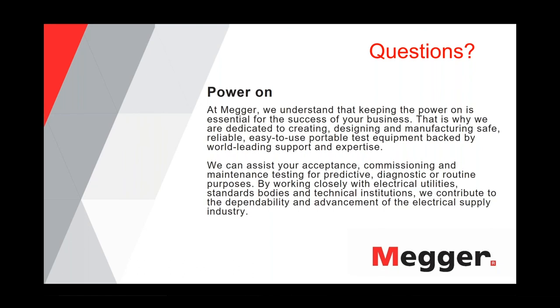there's an asset management view on this as well, because you want to do the testing as much as necessary and as little as you can get away with. So it makes sense, because everybody wants to optimize where to put the money and how much money to spend. Now, on a service aged cable, if you really have water treeing, the test that brings that out, first of all, to know it, would be the tan delta test, and then to have the go/no-go that the insulation is still good for a certain amount of time, that is done with the VLF test.